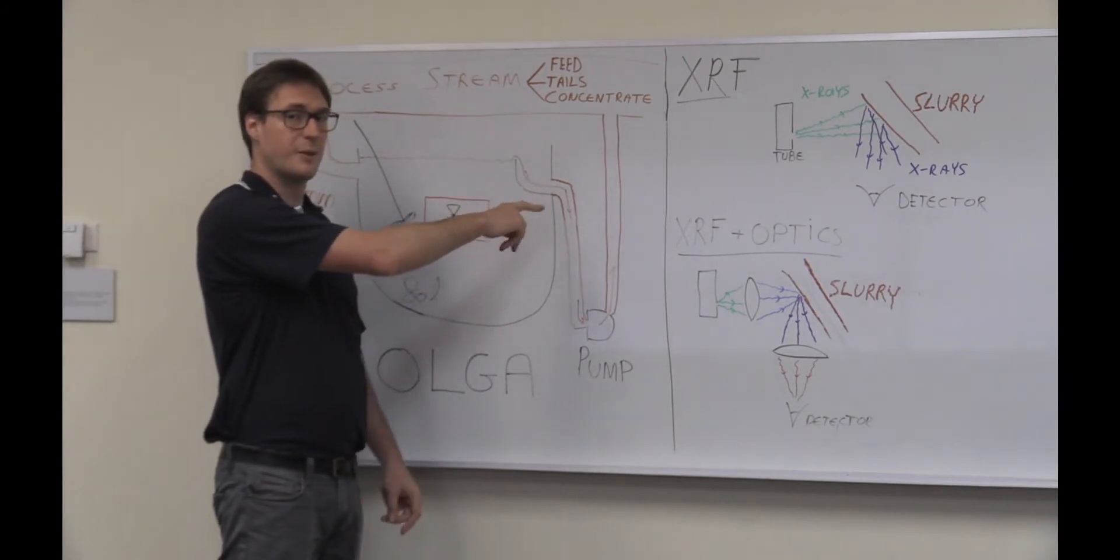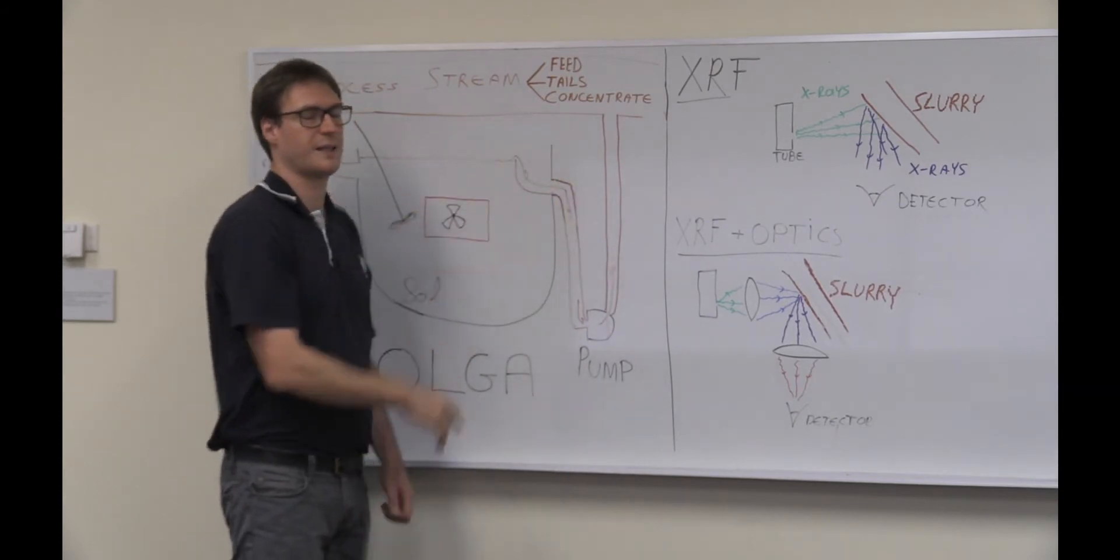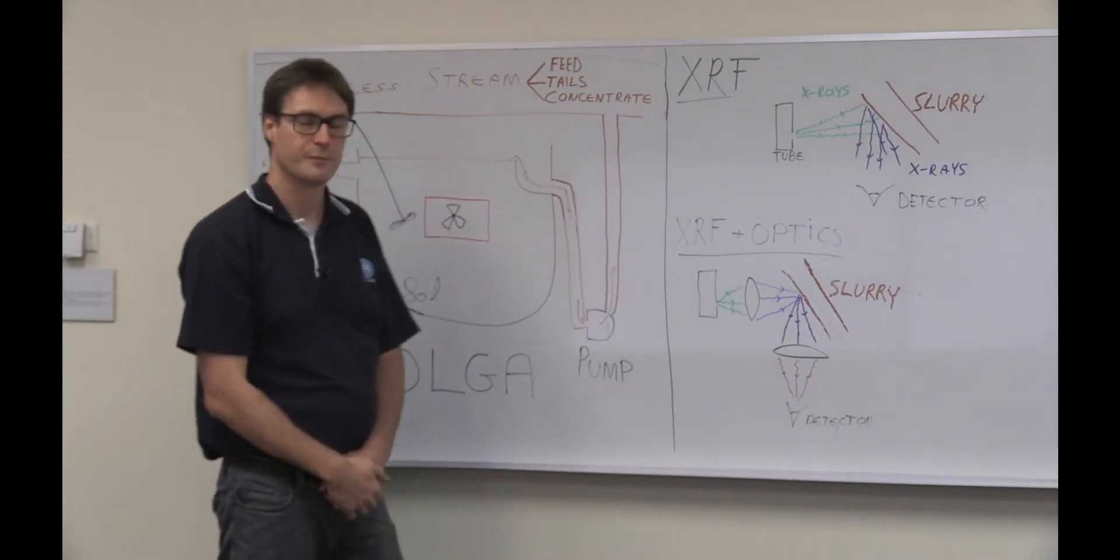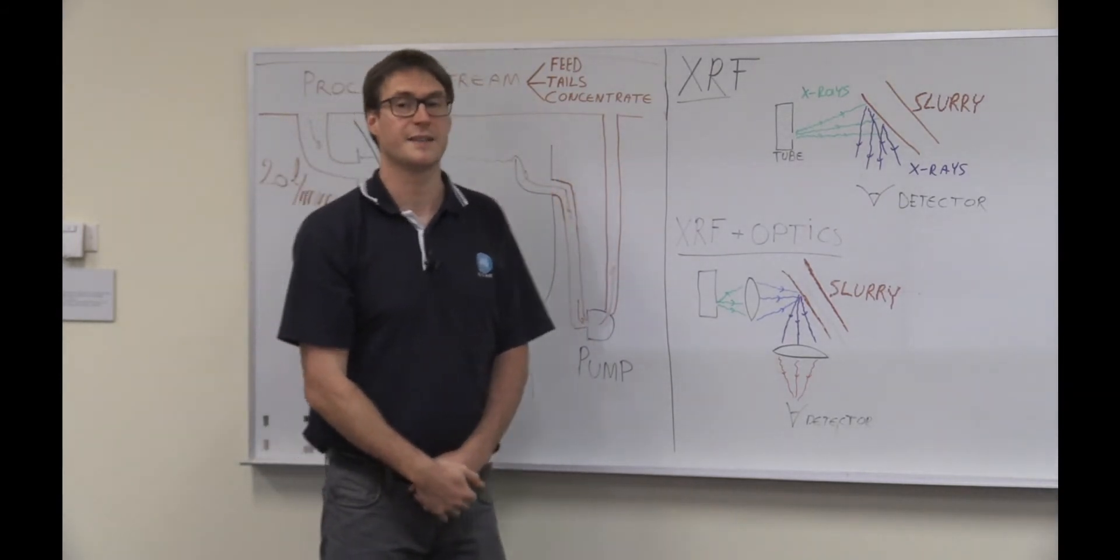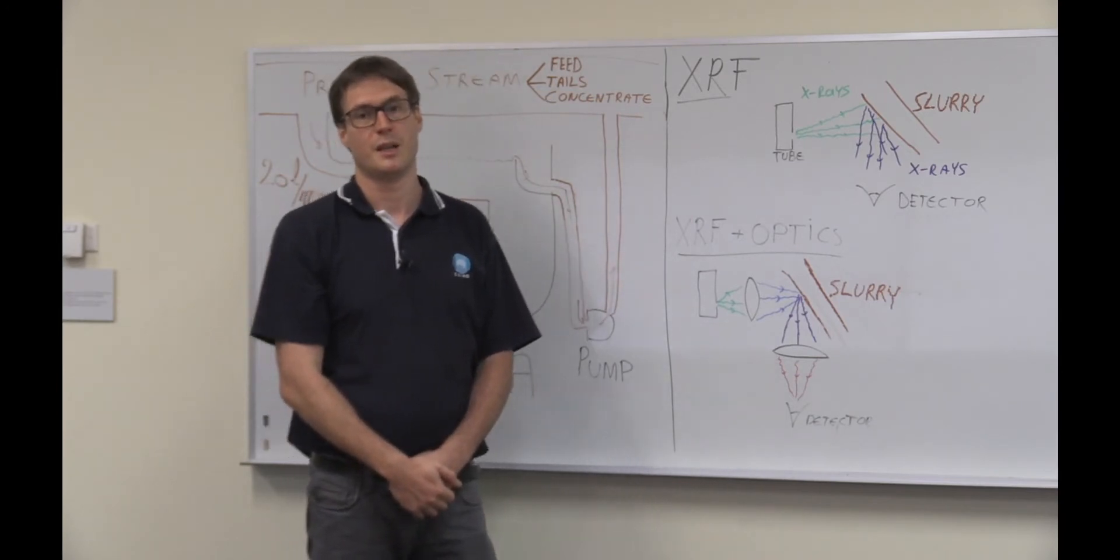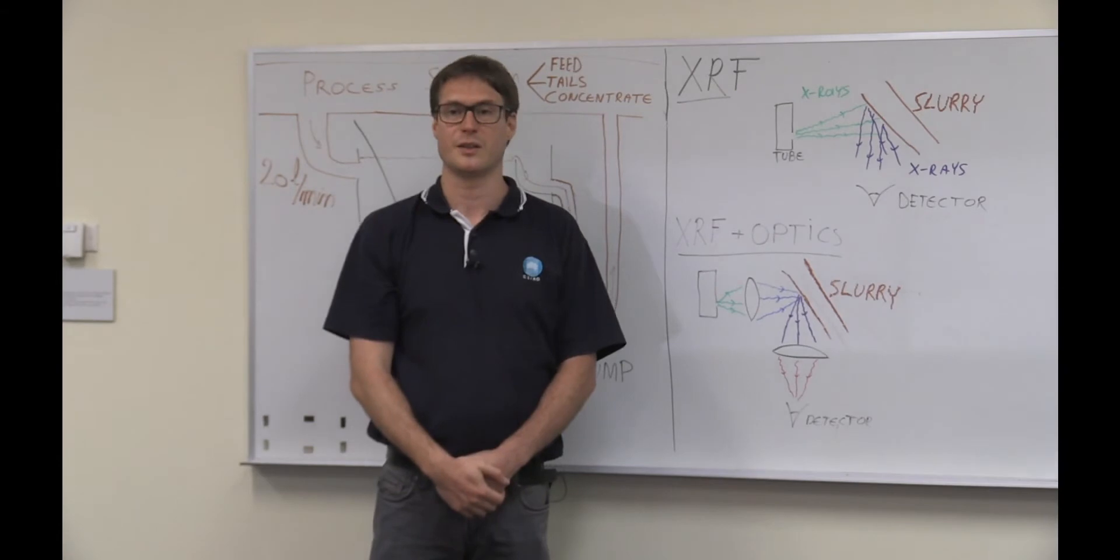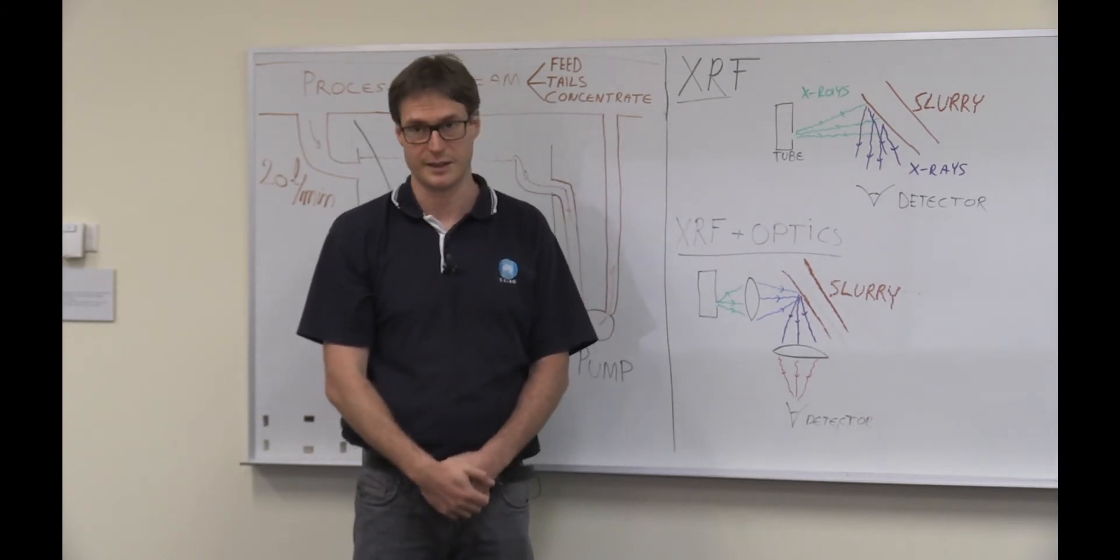On this side of the tank we have an overflow where the slurry leaves the tank and is being pumped back to the main process stream. Now a plant that has access to this online data of gold concentration can do online process control by, for example, looking at sudden increases in gold concentration in the tailings and act on it.